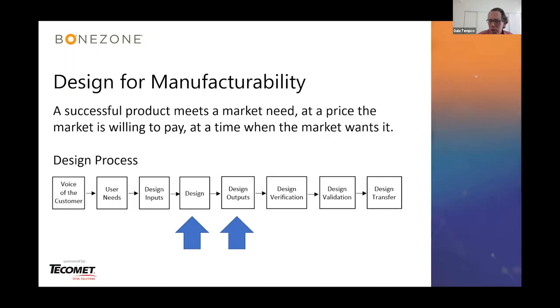But if we just take a very, very simple example, the voice of the customer says, hey, my instruments need to be safe. Okay, I'm doing surgical instruments, reusable, they need to be safe. Well, what does that mean? It's like they must be sterile and reusable. Okay, so if they need to be sterile, I'm going to put them in an autoclave. That's a user need. And then the design input is I need to make these from a material that can hold up to multiple autoclave cycles. And eventually the design output is I'm going to make it out of 17-4, some stainless steel I know meets those requirements. Again, that one's very simple, but all of the voice of the customer can be translated into user needs and design inputs and eventually design outputs, kind of following that train of thought.